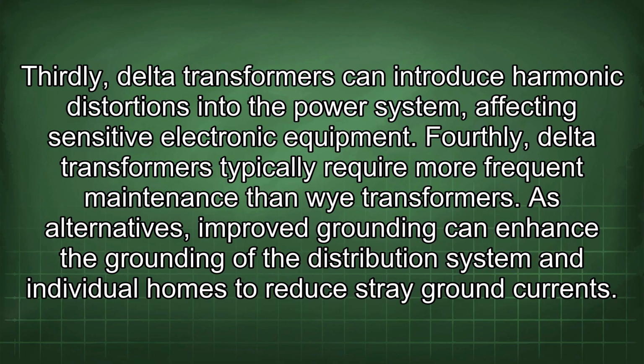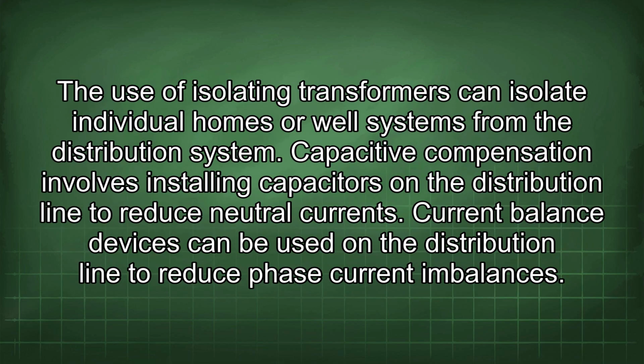As alternatives, improved grounding can enhance the grounding of the distribution system and individual homes to reduce stray ground currents. The use of isolating transformers can isolate individual homes or well systems from the distribution system. Capacitive compensation involves installing capacitors on the distribution line to reduce neutral currents. Current balance devices can be used on the distribution line to reduce phase current imbalances.